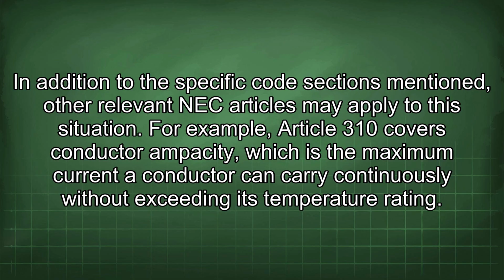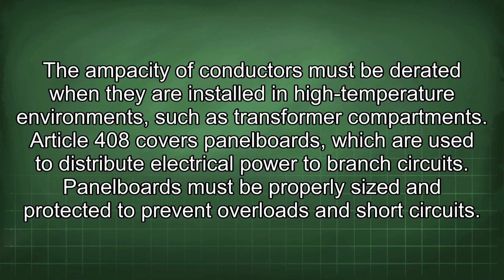In addition to the specific code sections mentioned, other relevant NEC articles may apply to this situation. For example, Article 310 covers conductor ampacity, which is the maximum current a conductor can carry continuously without exceeding its temperature rating. The ampacity of conductors must be derated when they are installed in high-temperature environments, such as transformer compartments. Article 408 covers panelboards, which are used to distribute electrical power to branch circuits. Panelboards must be properly sized and protected to prevent overloads and short circuits.